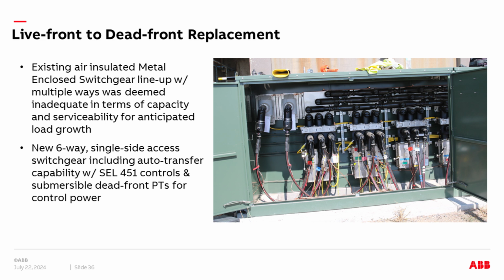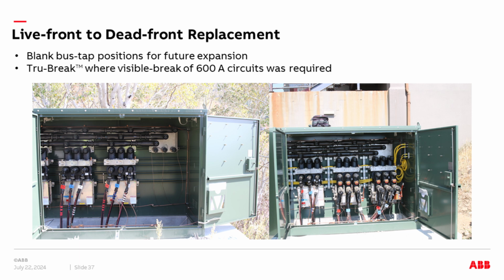This is an automatic transfer scheme, so you need a PT on each side for each source. So if you lose power on one side and you're switching, you still have power to run the controls on the secondary source. And here's another picture of the gear. It's too big to fit in one picture, so I split it. But you can see on the right side of the left picture is the space to accommodate a future way. So it's just active ports that are capped off there for another three-phase connection. And then on the right, you can see the fully loaded side of three of the ways.